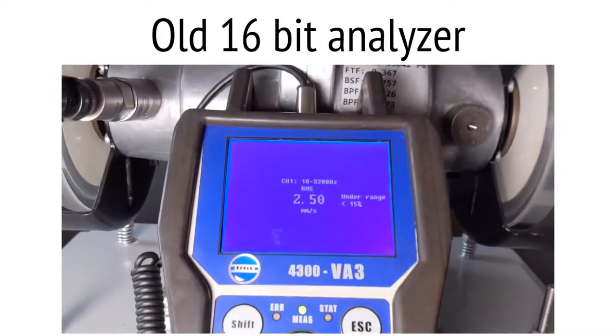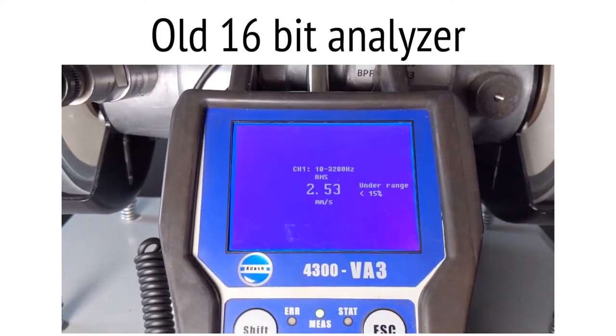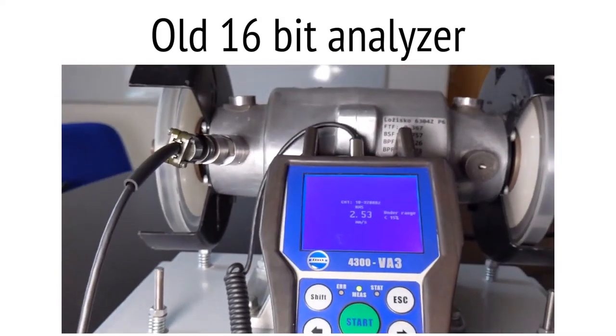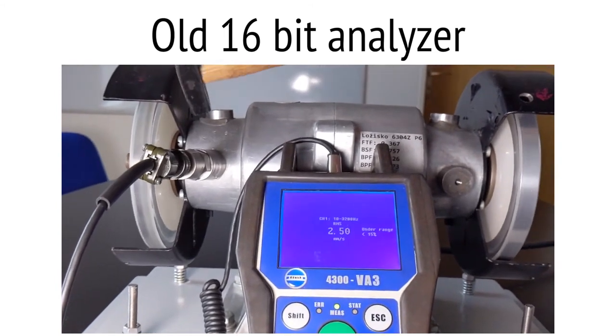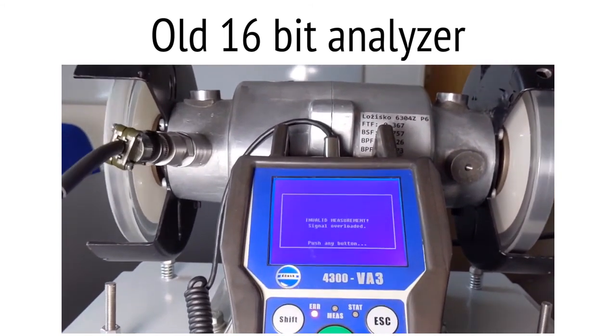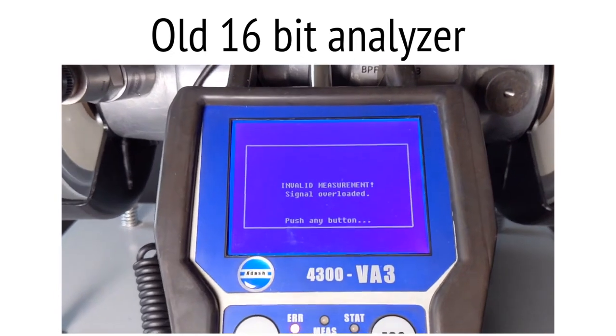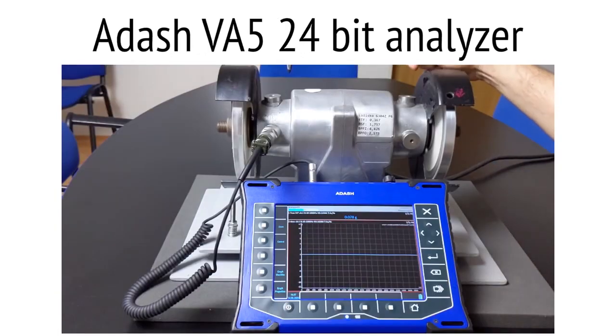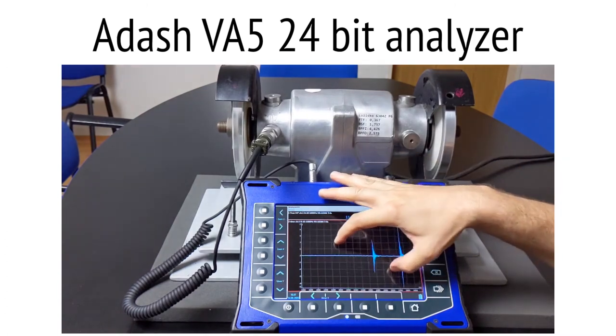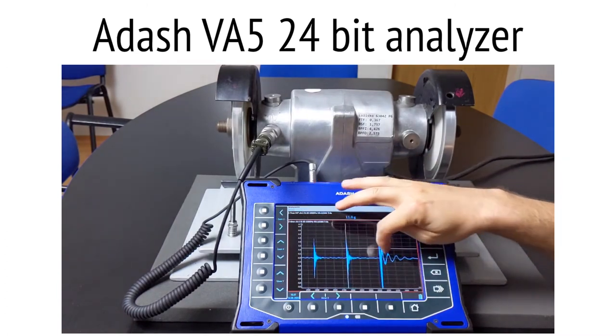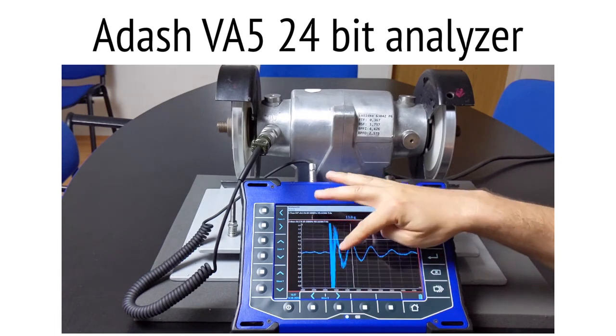This is an old Adash analyzer with a 16-bit converter. If the unexpected shock comes, it ruins the measurement. The next example is with the Adash VA5 analyzer. It contains a 24-bit converter. We measure the machine and again unexpected shocks come. The measurement continues without any problem.